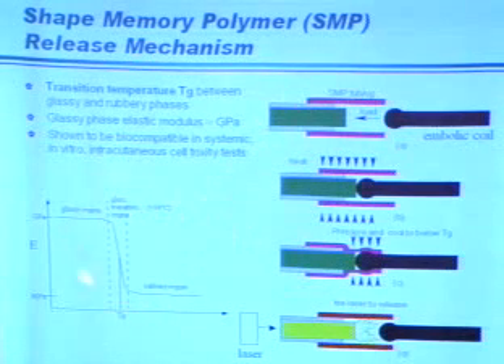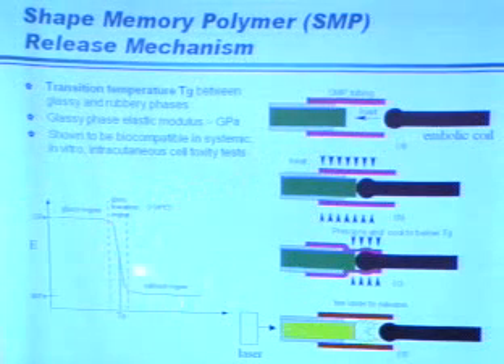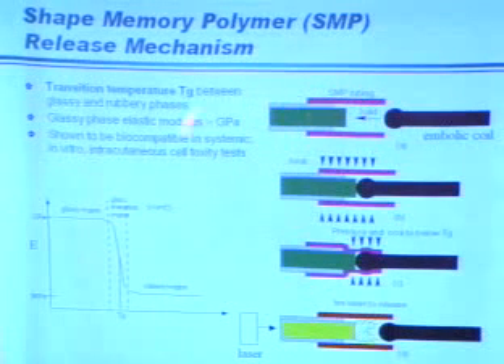But the memory stage again is the high temperature rubbery region. So it's the opposite of shape memory alloys. And how we designed this again is using a fiber optic instead of using electrical current, putting it in the end of the coil here. If you put it in and heat it up, it becomes very soft, again 400 times softer. You can apply uniform pressure to conform this material around it, and once you cool it down, it locks in. Because remember, the memory position is the high temperature position.